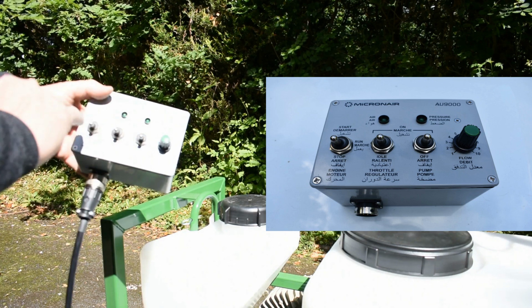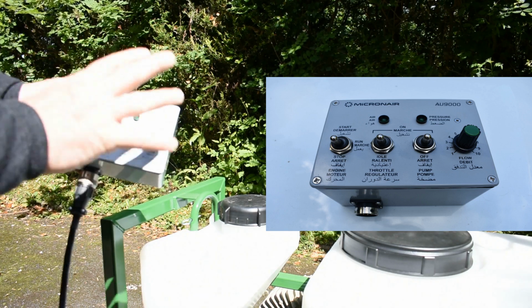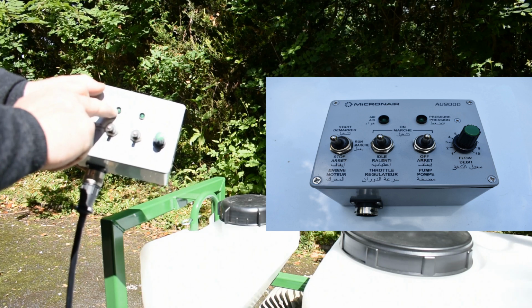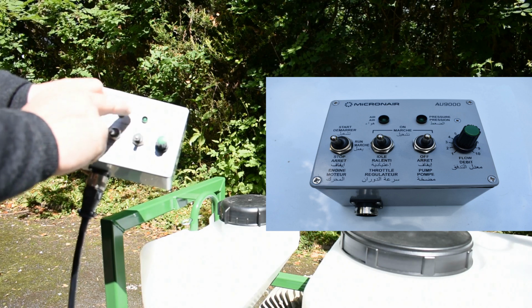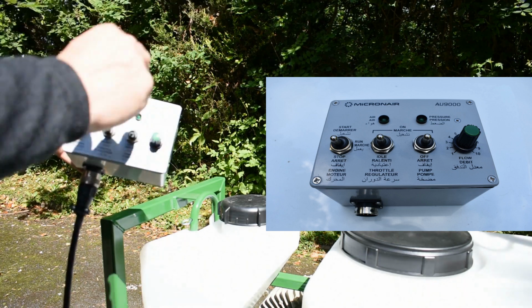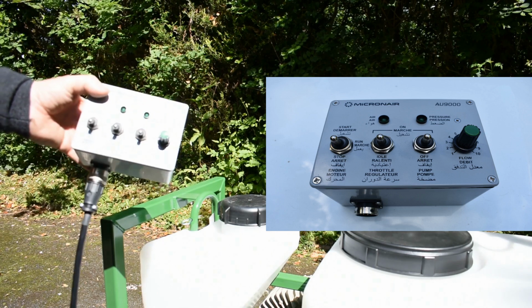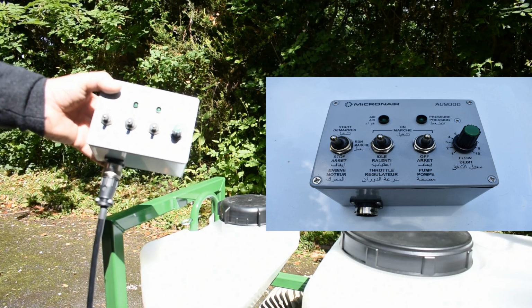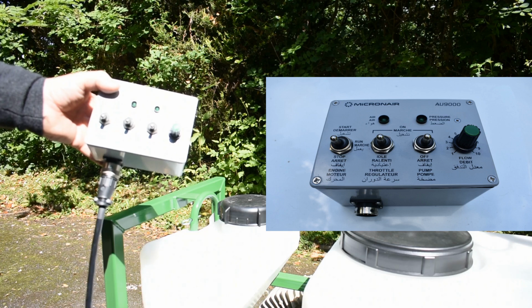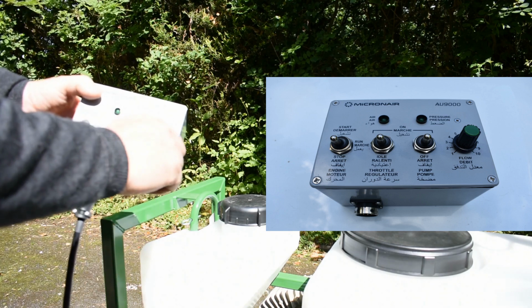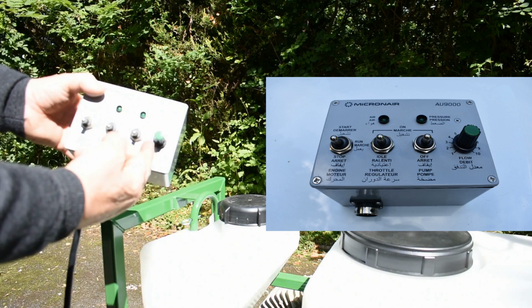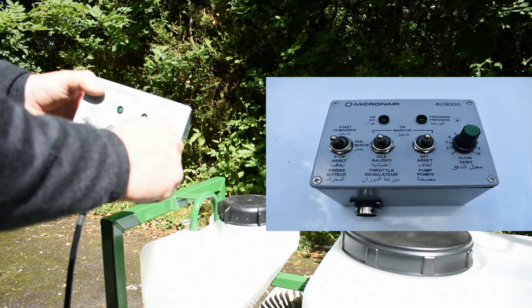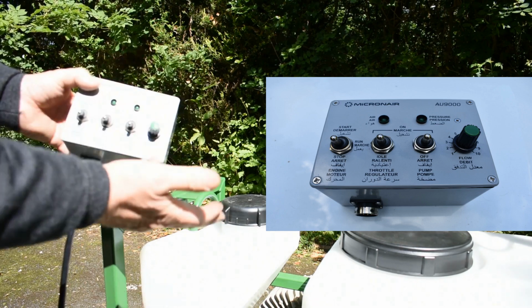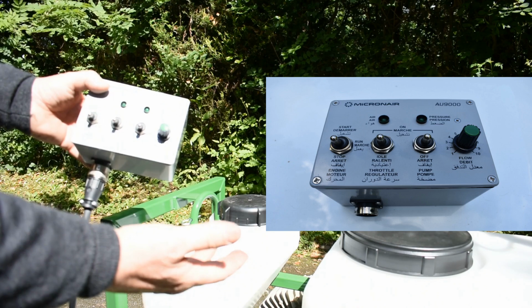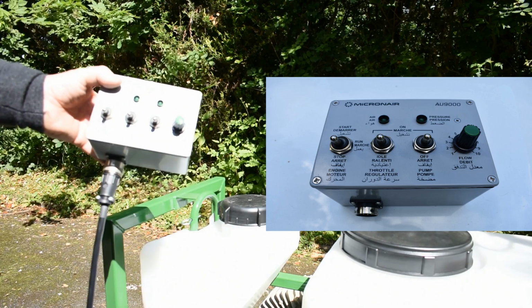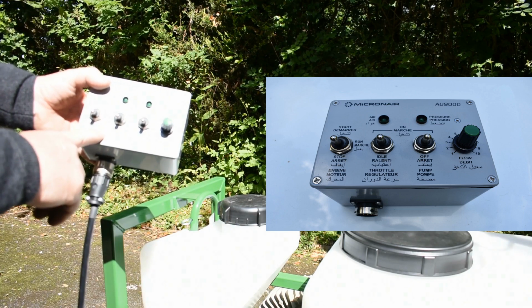On the top here you have indicator lights which are not operating at the moment, but normally when the pump is running and the airflow is running, you would have both lights indicating that everything is working properly. And then we control the flow selection by adjusting this rotary switch. Increasing the number is increasing the flow rate, and there's a calibration chart which is in the instruction manual to give the flow rates.